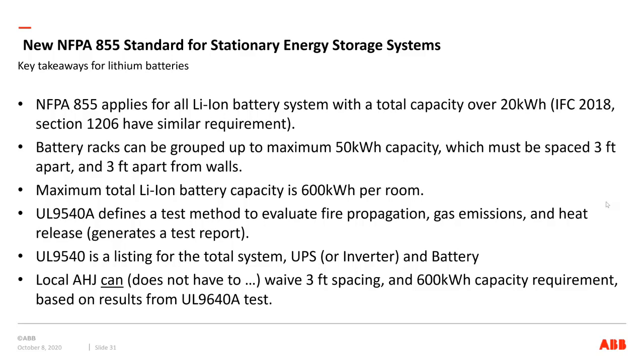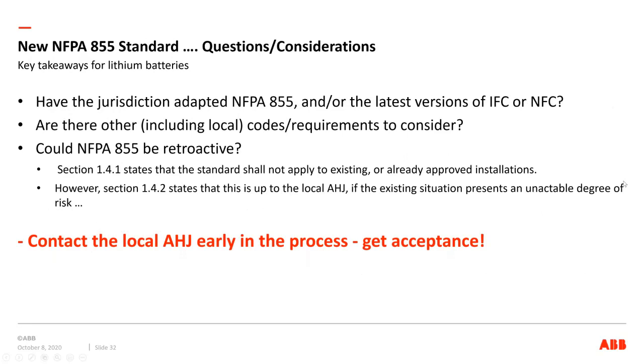We don't expect there would be a problem with installing them next to each other after passing the test, especially if they have the 9540 listing, which requires that the battery be listed together with the UPS, or, if it's an energy storage system, together with the inverter. And then to the next slide, which I think is the last one. It's just a couple of things to bear in mind. As I mentioned, the world is still learning, and the US market is still learning about this 855.